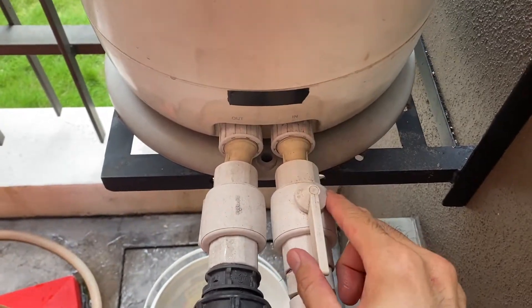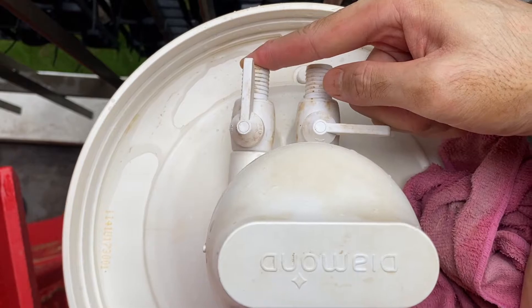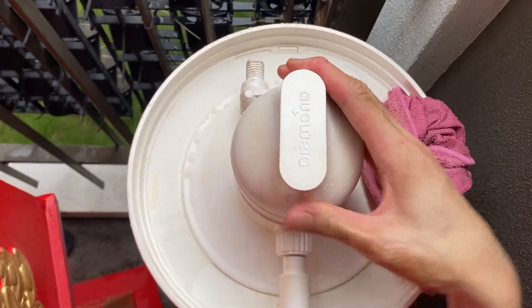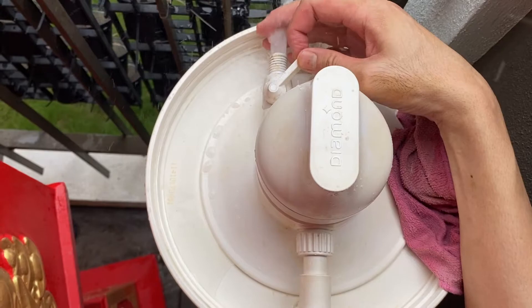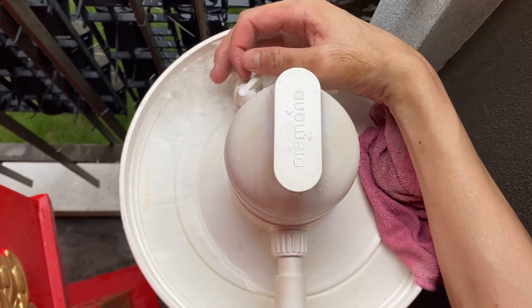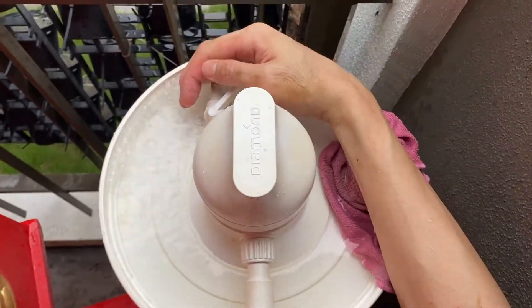Turn on the inlet and release the water at both positions — backwash and filtering position. You need to open the valve slowly and gently to remove all the gas, a process called degassing. In the backwash position I'm also performing degassing, used to remove all the air that's been trapped inside this chamber.